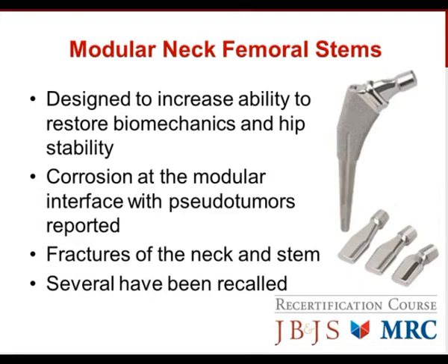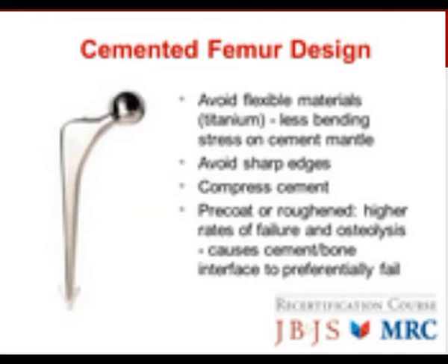Modular neck femoral stems have lost their popularity recently, but were in fairly widespread use a number of years ago. I think it's important to be familiar with this implant. They were designed to increase the ability to restore biomechanics and hip stability through these interchangeable modular necks. The problem with these implants included corrosion at the modular interface as well as fractures of the neck and stem. Several of these implants have now been recalled.